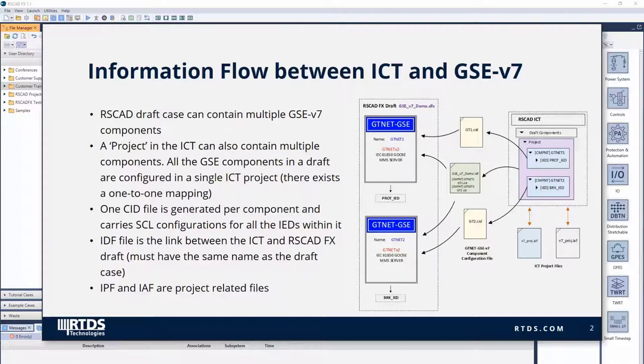The ICT also creates two other project-related files — the IPF file and IAF file — which are entirely for the use of the ICT. These two files should be included when sharing an RSCAD draft case so the receiving party can modify any of the GTNet GSE V7 components. Inclusion of the CID and IDF files is sufficient just to compile and run a case.